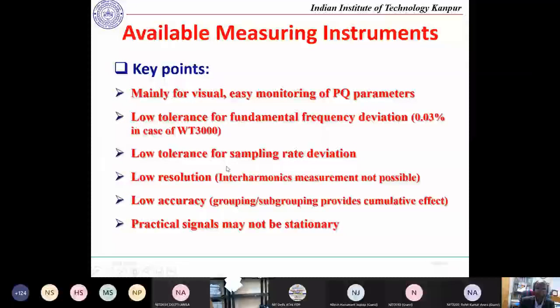Low tolerance of sampling rate deviation also causes a lot of problems. What I mean by sampling rate: suppose for a 50 Hertz cycle you take one complete cycle of data, but by mistake you take 1.1 cycles instead, not an integer multiple of the cycle. Once you are capturing data, you don't know, because there will be harmonics, zero crossings, etc., and you may miss them, giving you the wrong result.